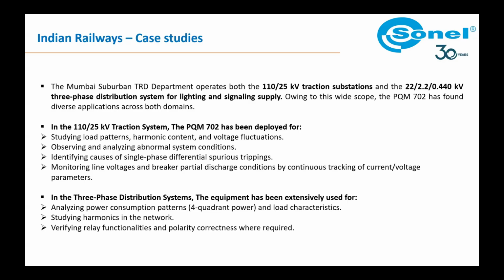because Mumbai is a place prone to rodents and other animals. Squirrels can damage the cables, and these things can cause any issue. We were looking everywhere to find out why this fault was happening, why there was differential transformer tripping. Differential tripping is a very serious tripping, and we can't just charge a transformer on our intuition. So we needed to identify what caused the tripping, and it became a very big issue for us.